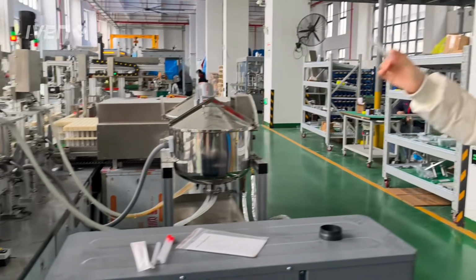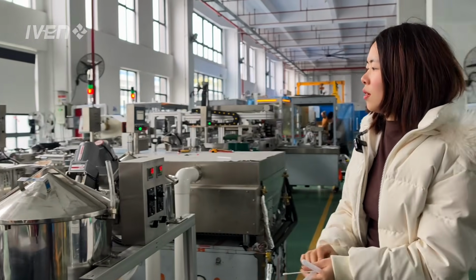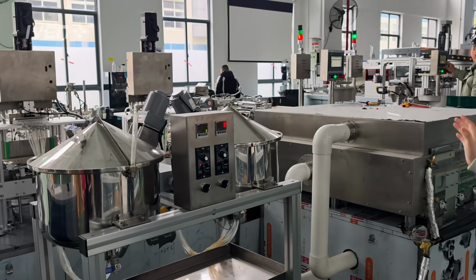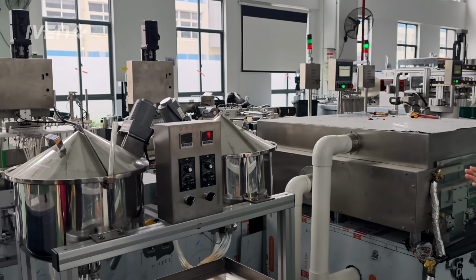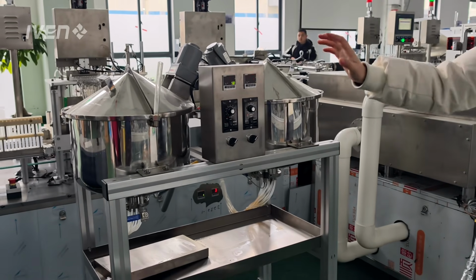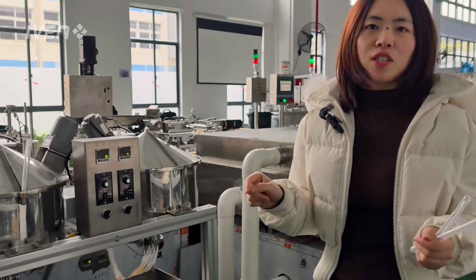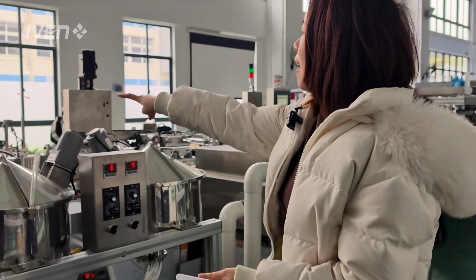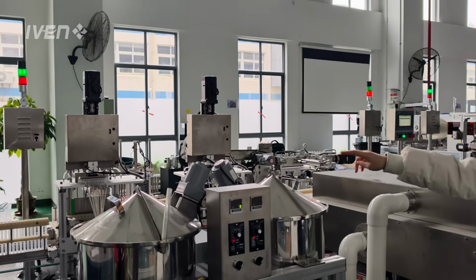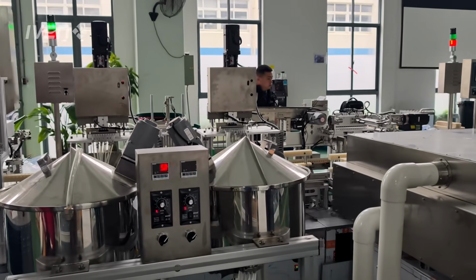And then after the tubes loading, it's going to the dosing stage. There are 2 mixing tanks. These 2 mixing tanks, it's not like one in use, one standby. They work at the same time, but the medium feeding in these 2 tanks are different. That means we have 2 stations for feeding, and both of them have 10 feeding needles.